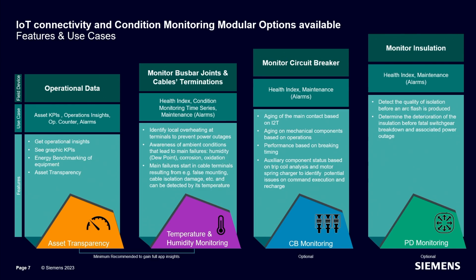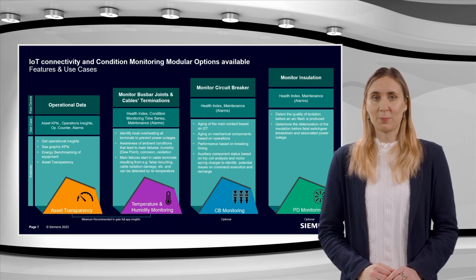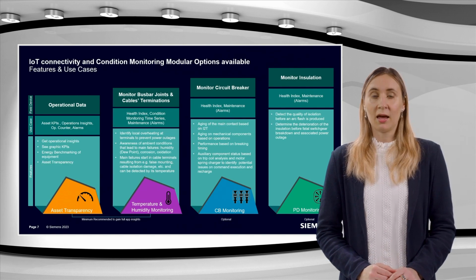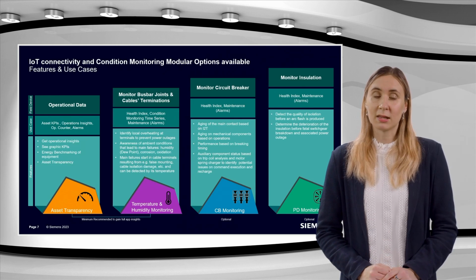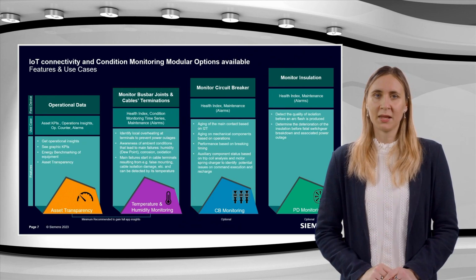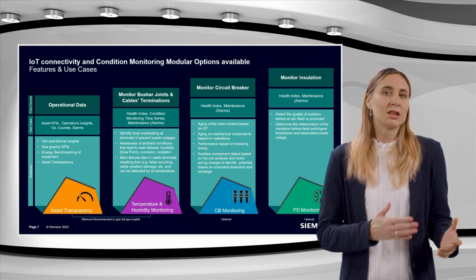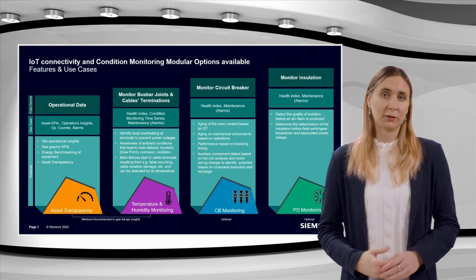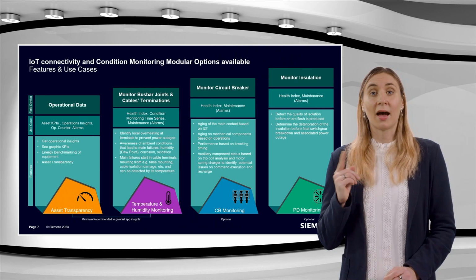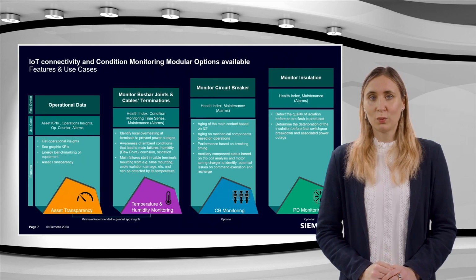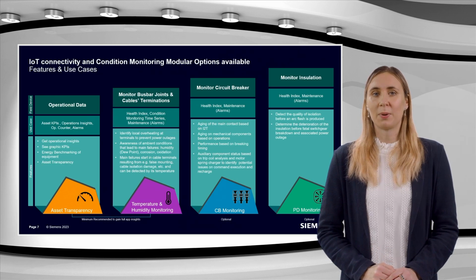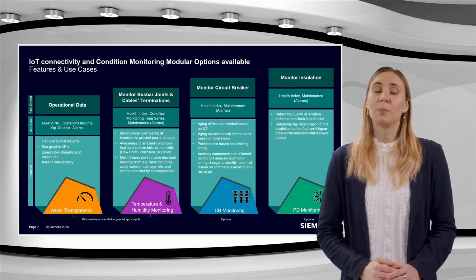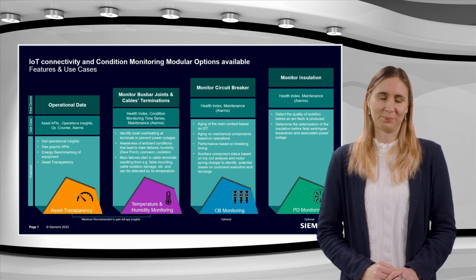Condition monitoring can be divided into three modules. First, temperature and humidity monitoring, where we can detect loose connections—for example, screwed busbar connections or cable terminations—and inadequate contacts, for example with the withdrawable circuit breaker. This can arise from the fact that instead of the necessary torque of M12, only that for M10 was used at high speed. We identify local overheating at terminals to prevent power outages and avoid failures due to corrosion or oxidation.